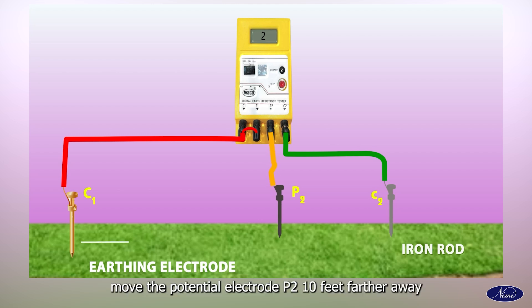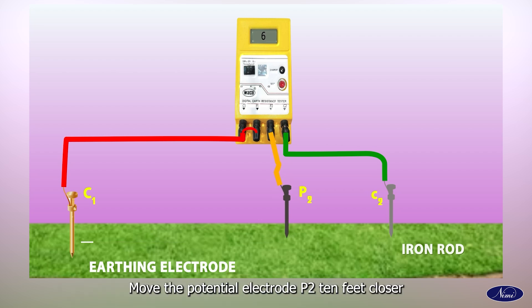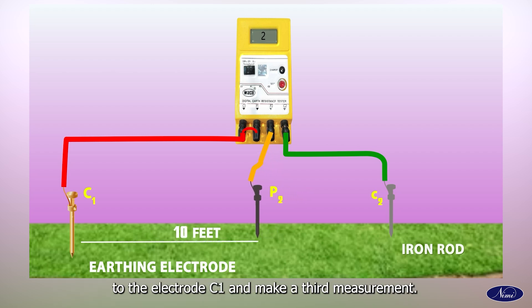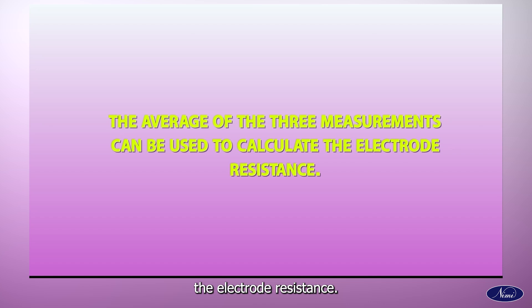Move the potential electrode P2 10 feet farther away from the electrode C1 and make a second measurement. Move the potential electrode P2 10 feet closer to the electrode C1 and make a third measurement. The average of the three measurements can be used to calculate the electrode resistance.